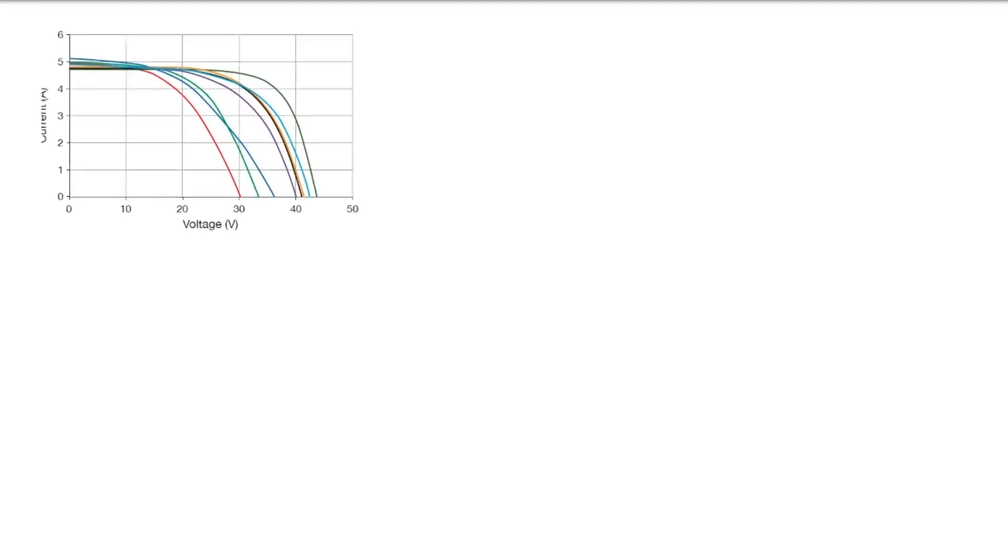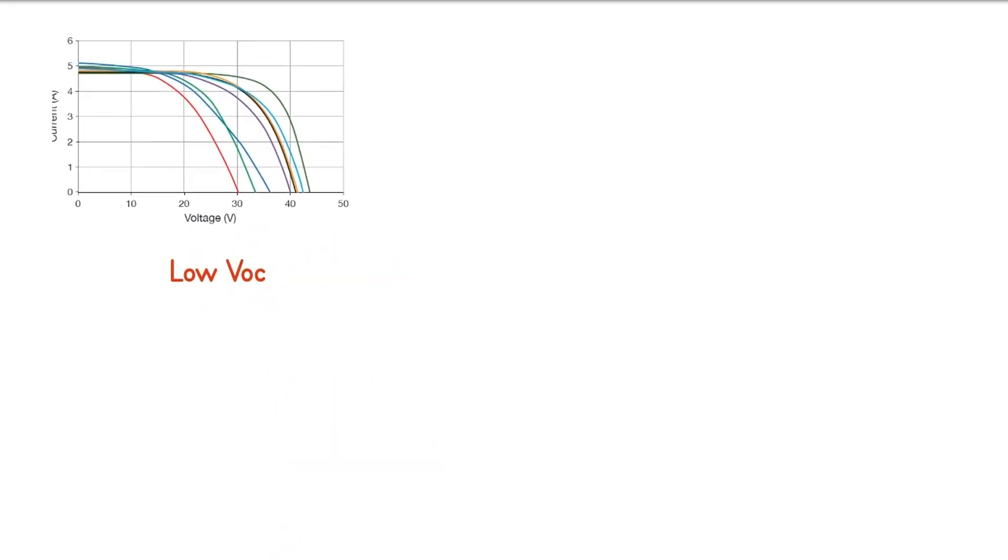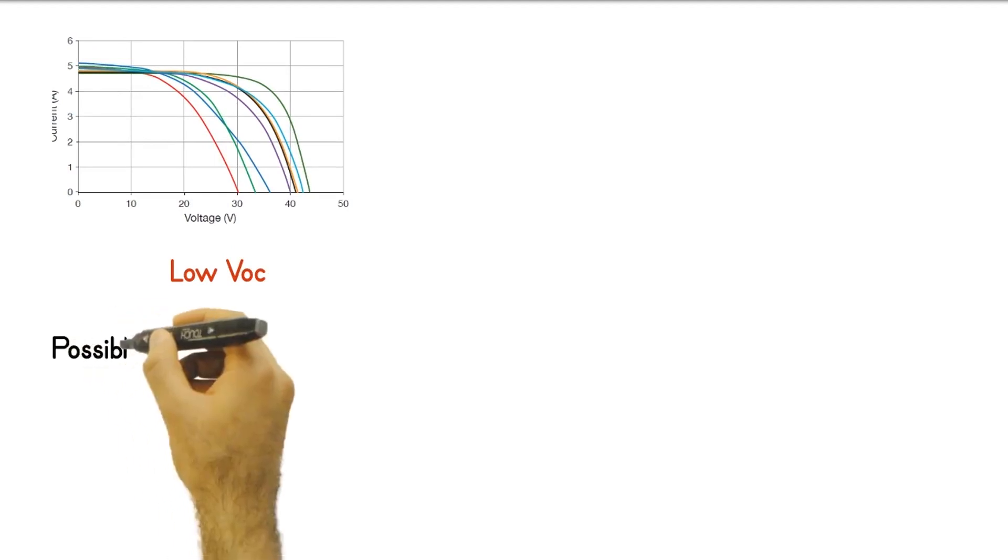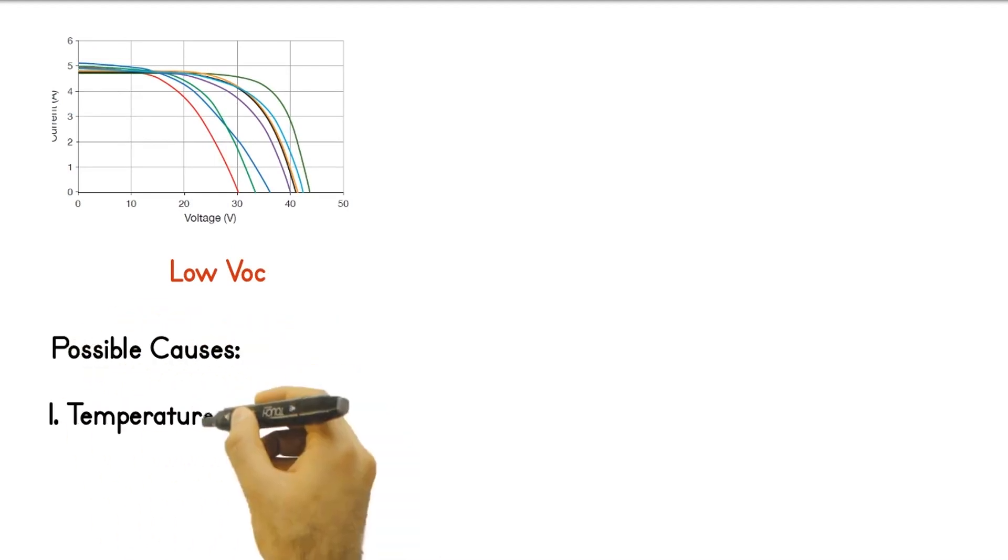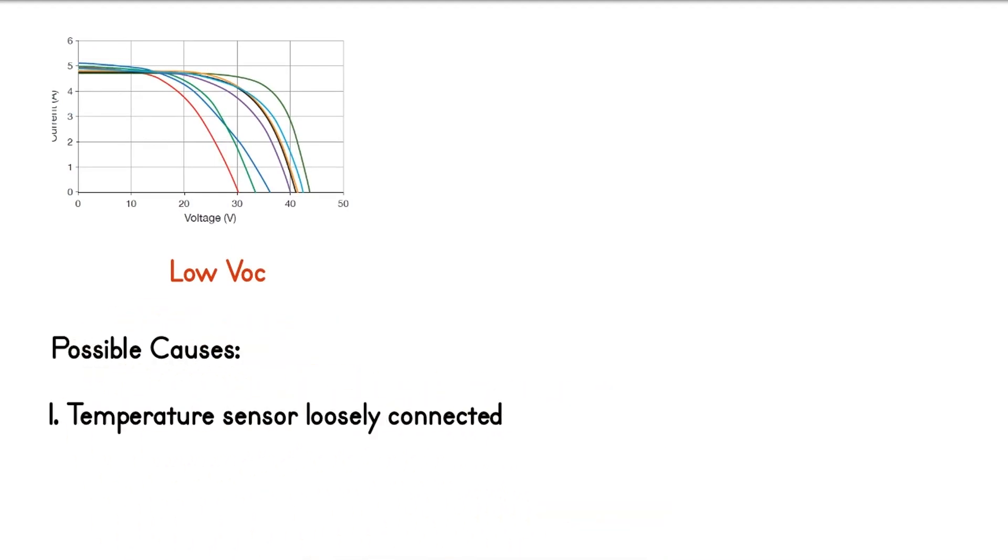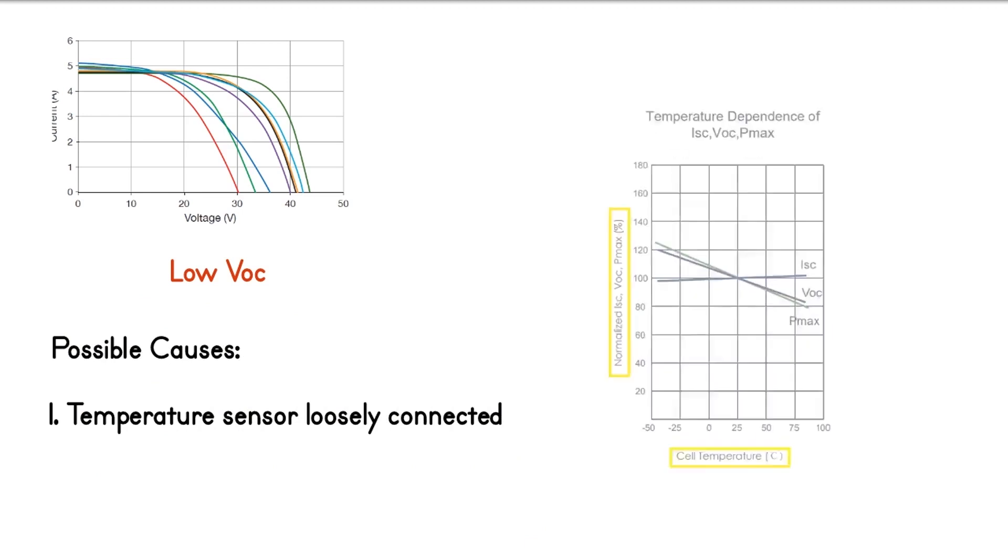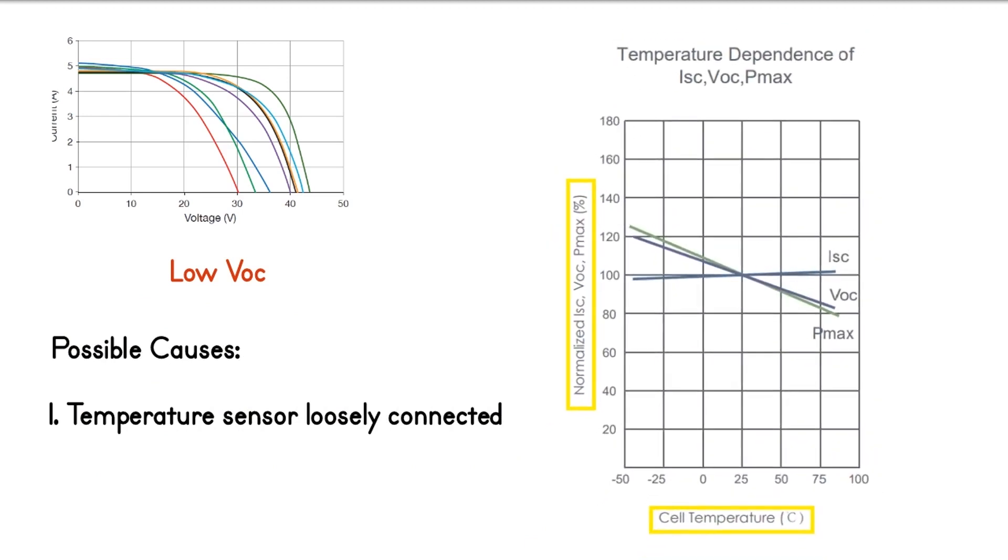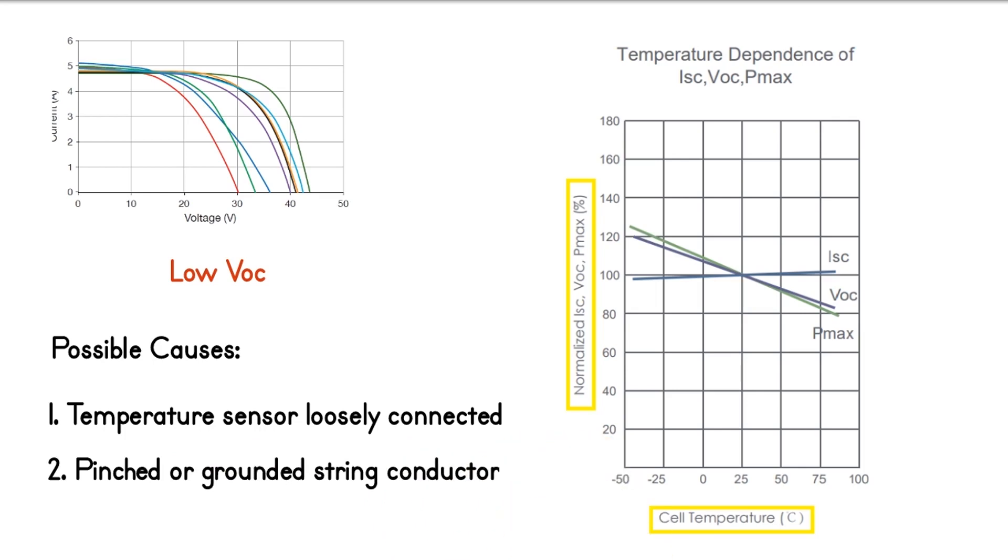The third type of deviation is low open circuit voltage or VOC. When IV curve test returns low VOC, check if the temperature sensor is connected properly to the back of the representative module. There is inverse relationship between cell temperature and VOC. If the temperature sensor is not connected properly, the measured temperature will be lower and the predicted VOC will be higher than that of the measured curve. Pinched or grounded string conductor returns low VOC during test because it essentially shortens the length of the series string under test.